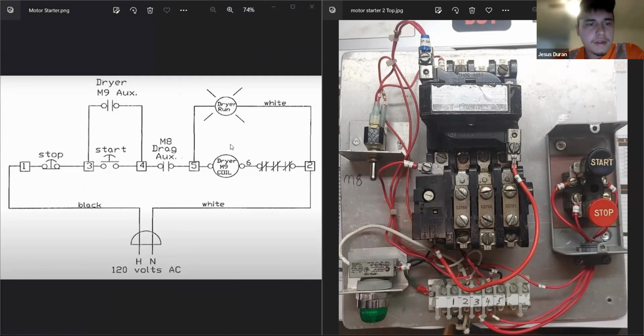If the button's pushed, help them out - if your button's pushed, pull that coil in. Okay, the only purpose is this comes in after the fact. This here closes only after you get this thing here to move. This thing hasn't even moved yet, so you can't be picking on that circuit. We've got to get 120 volts to this coil here, and it's not gonna go through there, it's gonna have to go through this right here.